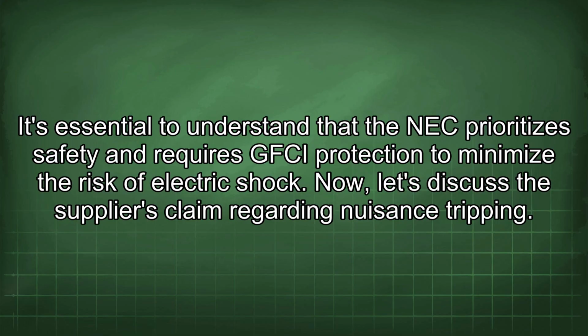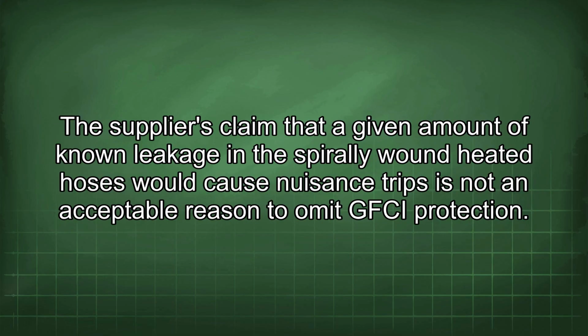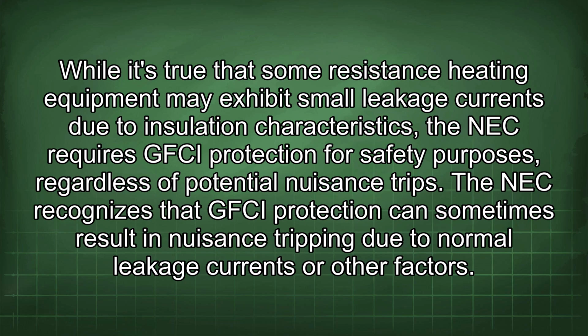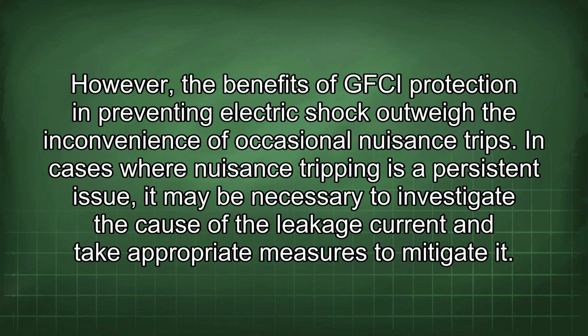Now let's discuss the supplier's claim regarding nuisance tripping. The supplier's claim that a given amount of known leakage in the spirally wound heated hoses would cause nuisance trips is not an acceptable reason to omit GFCI protection. While it's true that some resistance heating equipment may exhibit small leakage currents due to insulation characteristics, the NEC requires GFCI protection for safety purposes, regardless of potential nuisance trips. The NEC recognizes that GFCI protection can sometimes result in nuisance tripping due to normal leakage currents or other factors. However, the benefits of GFCI protection in preventing electric shock outweigh the inconvenience of occasional nuisance trips.